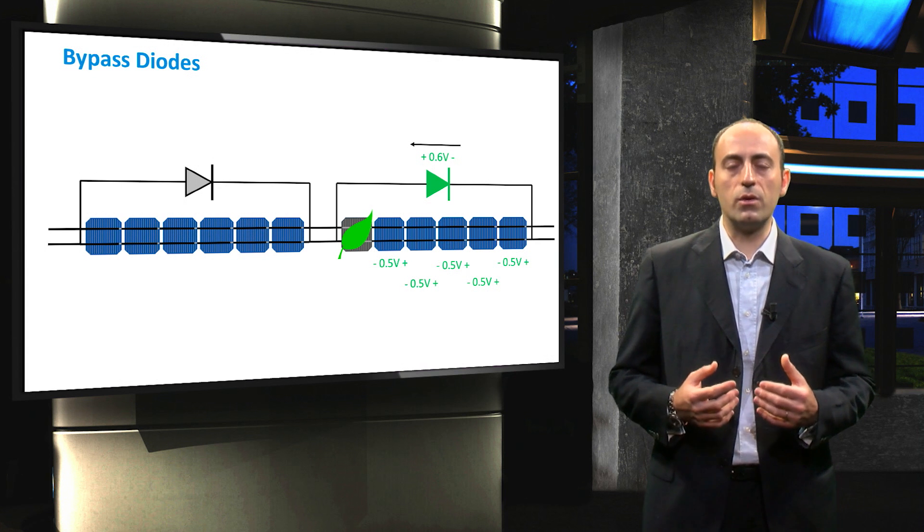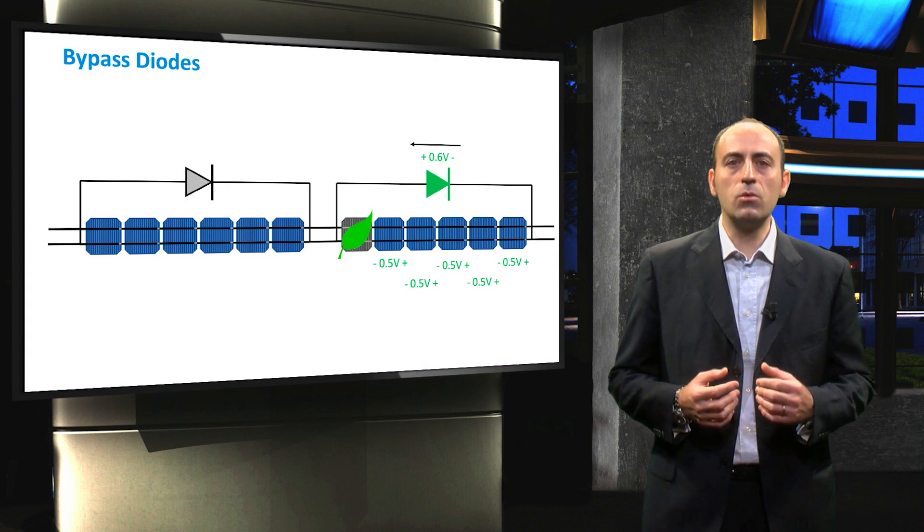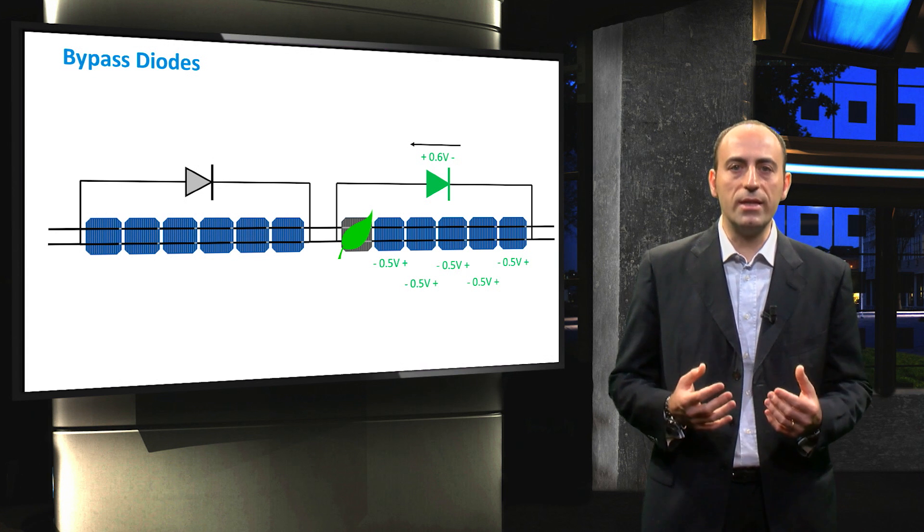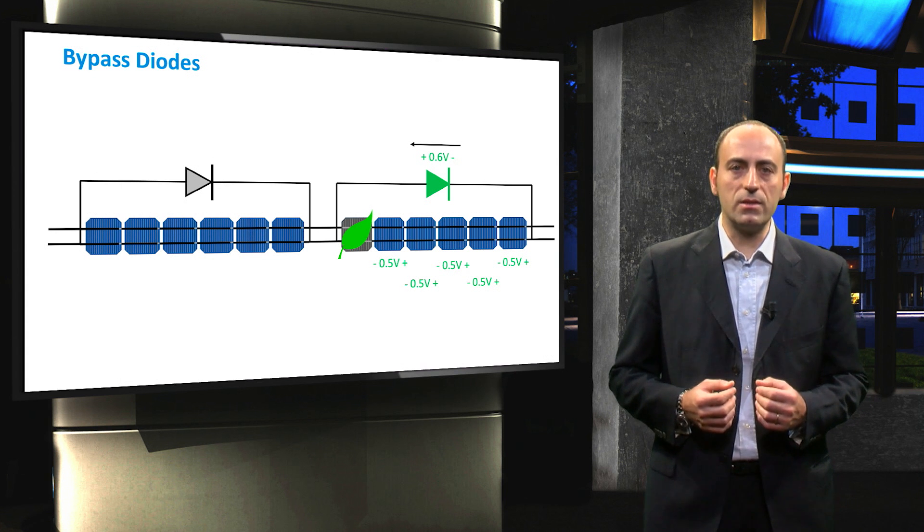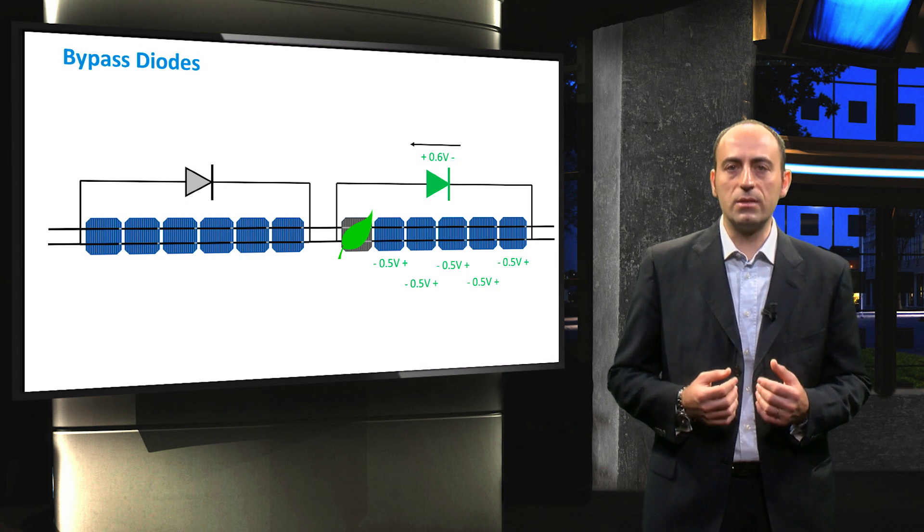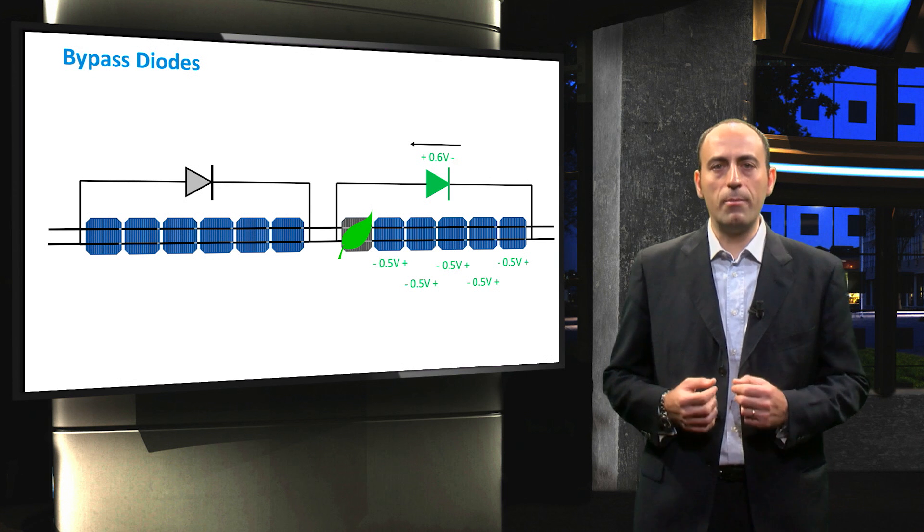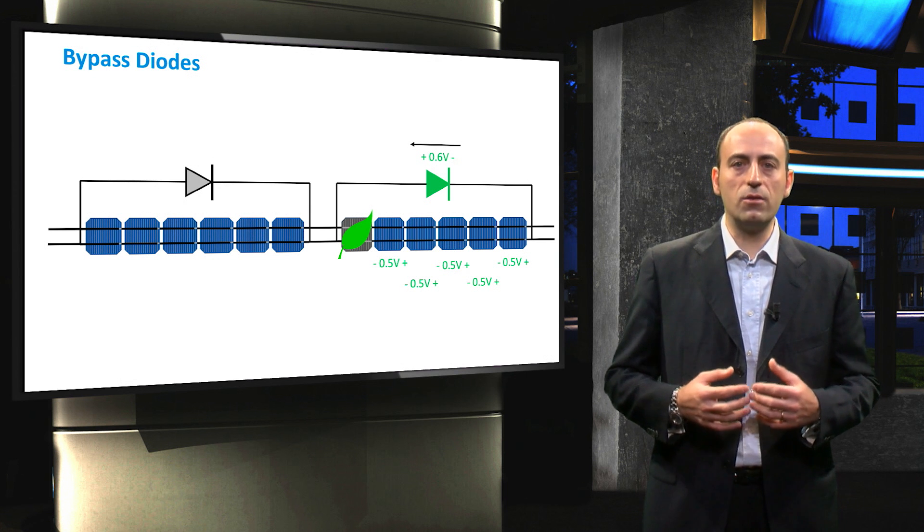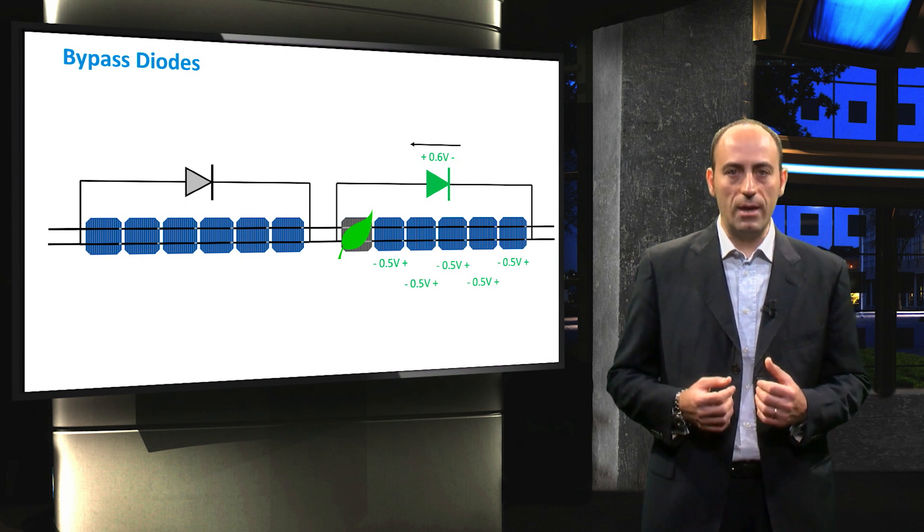The maximum power dissipation in the shaded cell is approximately equal to the generating capability of all cells in the group, and thus, for silicon cells, the maximum group per diode without causing damage is about 15 cells per bypass diode, which means that for a normal 36 cells module, two bypass diodes are needed to ensure that the module will not be vulnerable to hotspot damage.